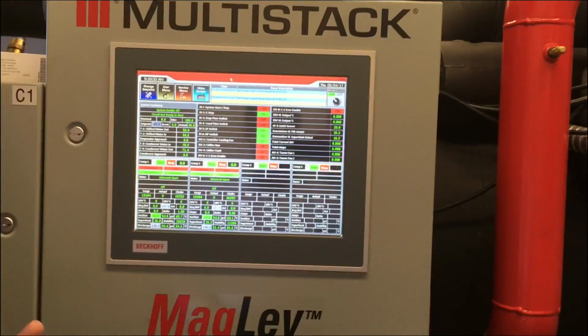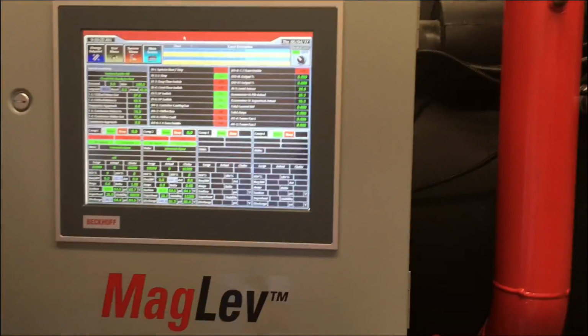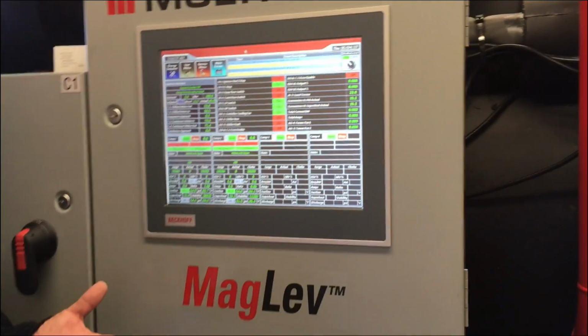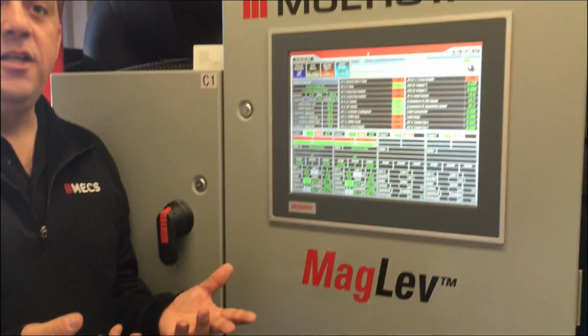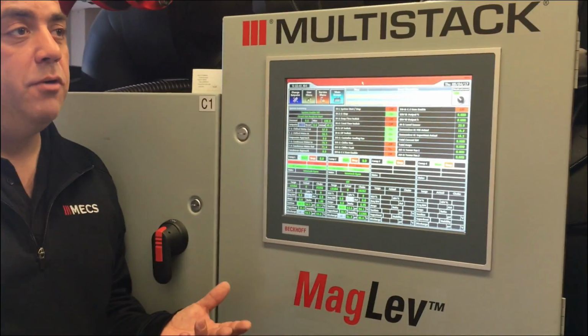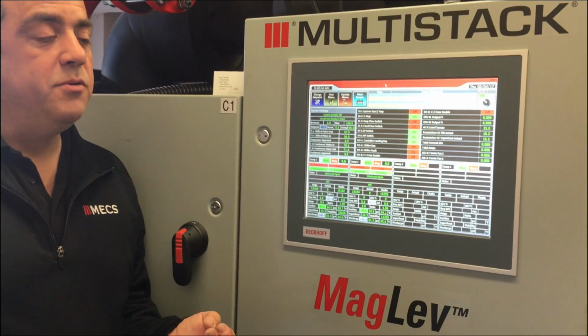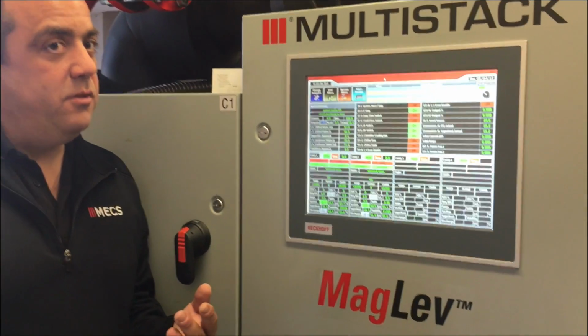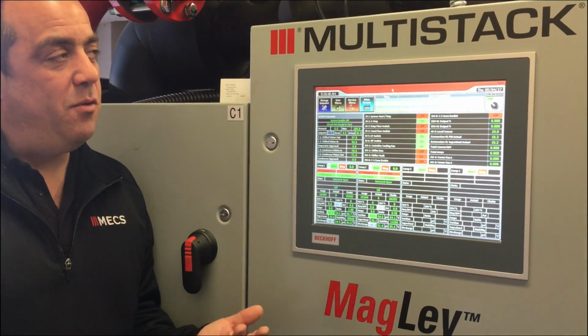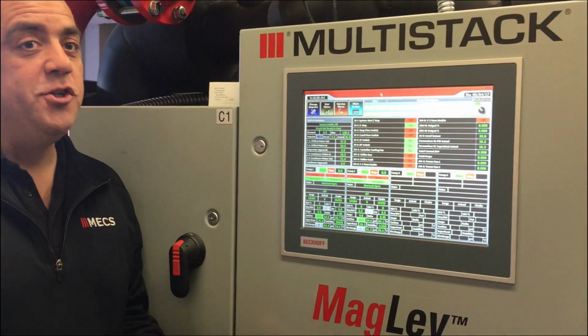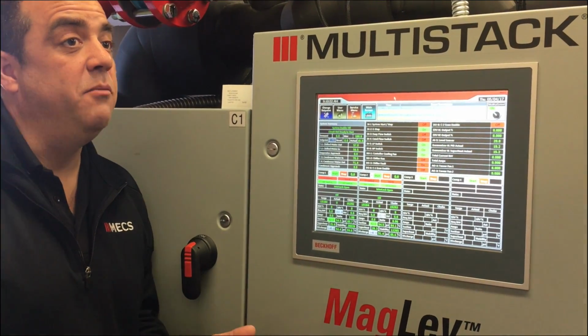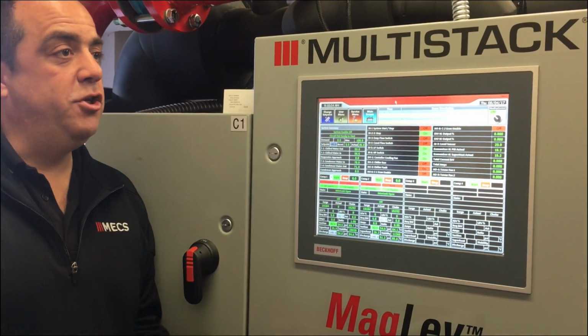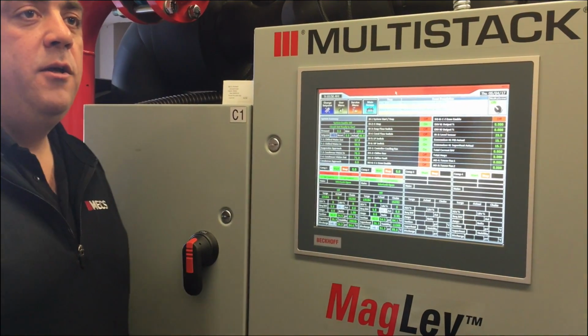We're looking at it 6,000 times a second to make sure that we can do it, because we're spinning it in a high 17,000, 18,000 RPM range while this thing is in full production, maybe as high as 20,000 RPM. So we're doing a lot to get that to happen. But what we do get is incredible efficiencies, because we have a very light spinning mass compared to a traditional centrifugal chiller that's got a 3-foot long flywheel.